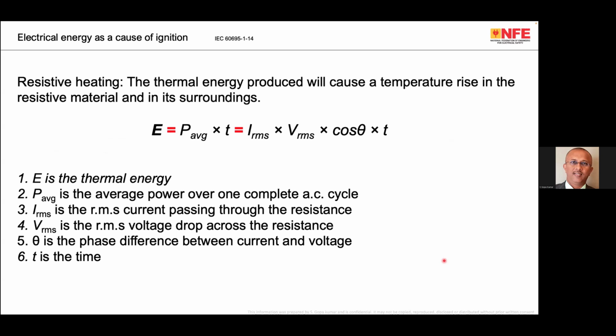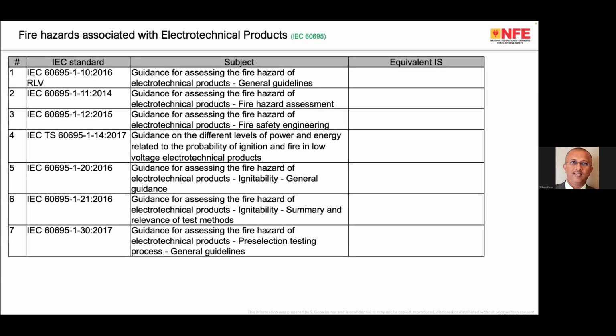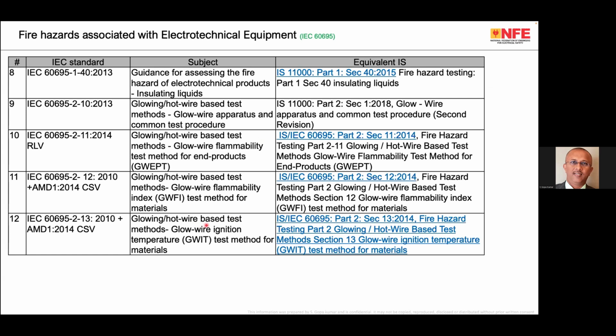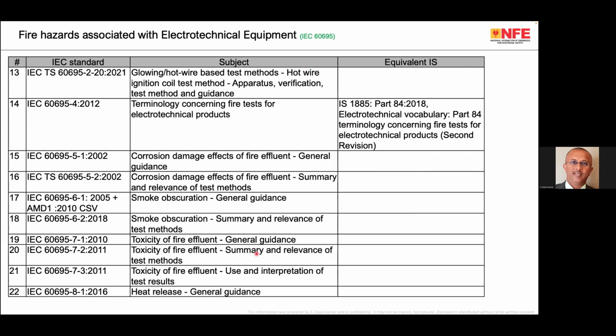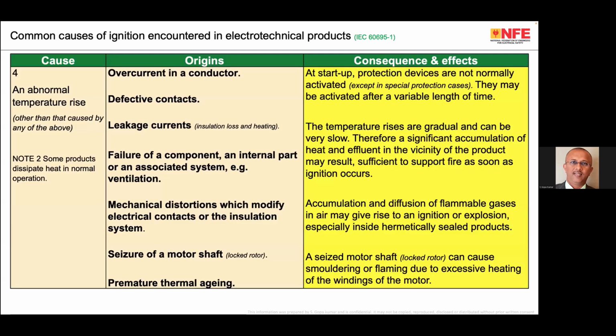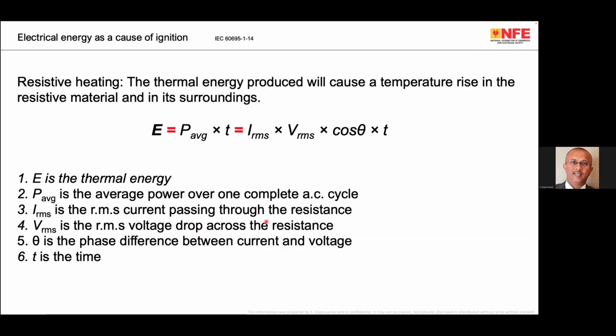Why this analysis is made is that, finally, it is the responsibility of the equipment manufacturer to take the equipment through various kinds of testing. For example, fire safety testing. Let me show you one of the tests: glow wire testing, a hot wire based test, the glow wire flammability test method for end products, glow wire apparatus and common test procedure. So basically each product undergoes certain tests. It is based on the type of equipment, the energy which is used, and in case of a fault, the duration, the time within which the devices are going to operate, and several influencing factors. You can have a look at the particular standard. You will get a lot of ideas.